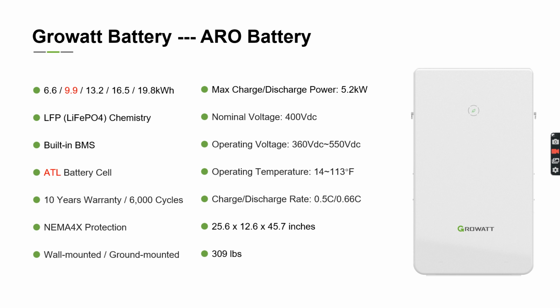Growatt's ARO battery is compatible with Growatt's XH inverter to provide a large capacity battery bank and up to 5 kilowatts of backup power for residential systems. This lithium-ion battery with built-in BMS has a 90% depth of discharge and a max charge or discharge power of 5 kilowatts. This battery, similar to the XH inverter, allows for a flexible choice of battery capacity from 6.6 kilowatt hours to 19.8 kilowatt hours. This ground or wall-mounted battery will remain operational from 14 degrees Fahrenheit to 113 degrees Fahrenheit and will include a 10-year warranty or up to 6,000 cycles.